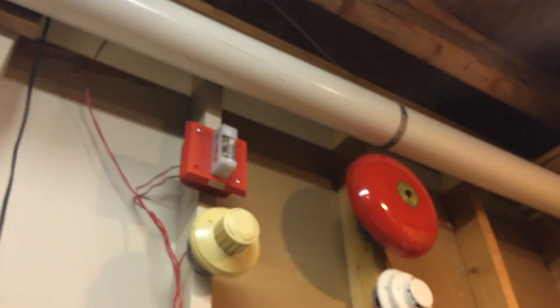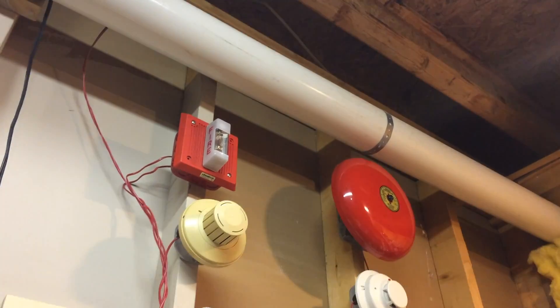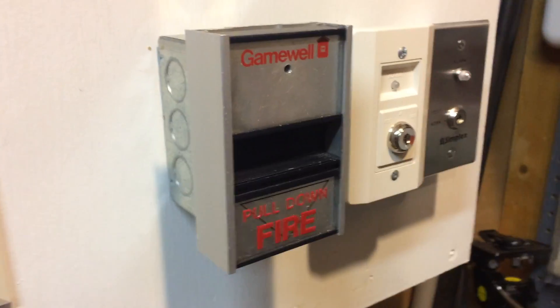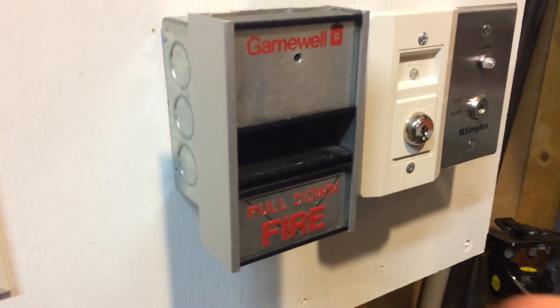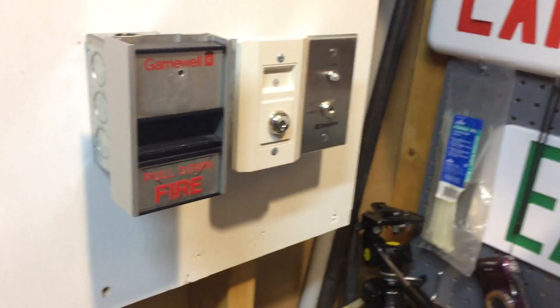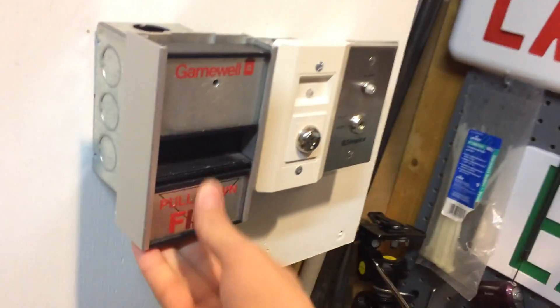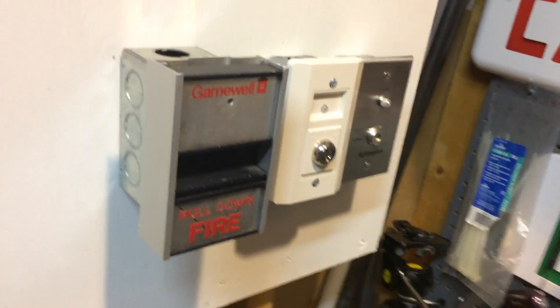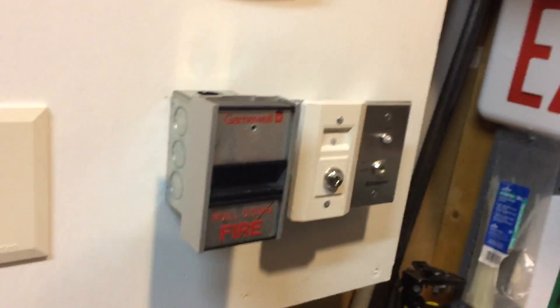There is audible silence on the Wheelock EH-DL1-WM-24. So now we'll demonstrate this other pull station, the GameWell M69. This pull station is really, really hard to pull. You might have seen some videos from other YouTube users about how hard to pull this one is — it is seriously really hard to pull. It's probably more than 10 pounds of pull force.